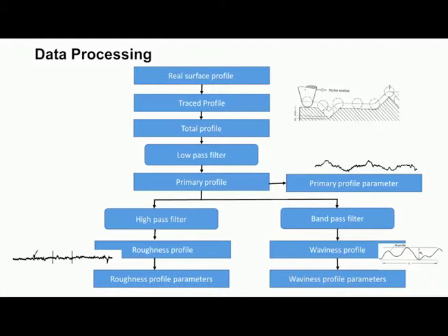That means the stylus of the surface finish measurement instrument should be moved on the surface to be tested. You can see here we have a conical stylus and then a radiused tip. This radius will be like 2 micrometer or 5 micrometer or 10 micrometer, and this stylus or probe tip will move on the surface.